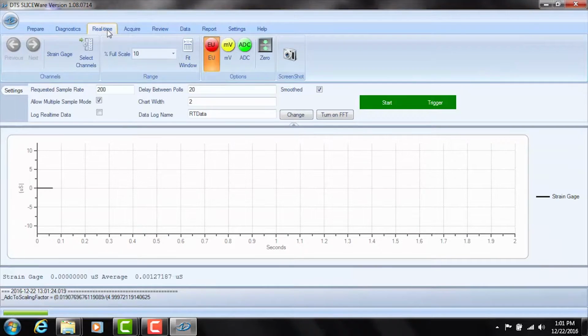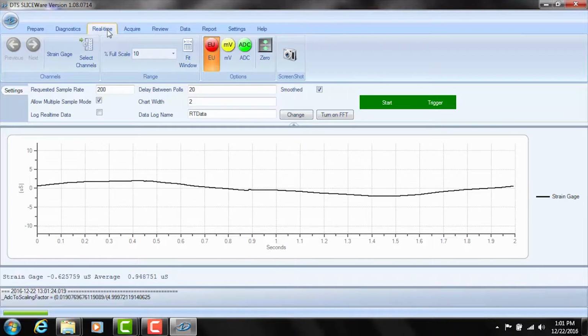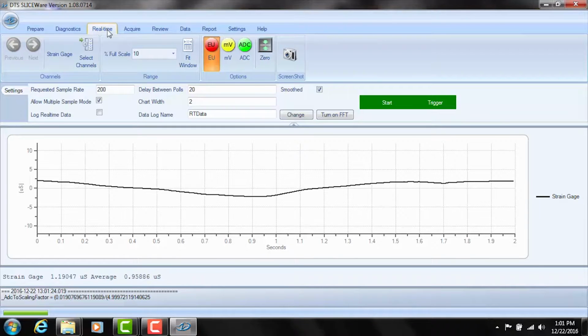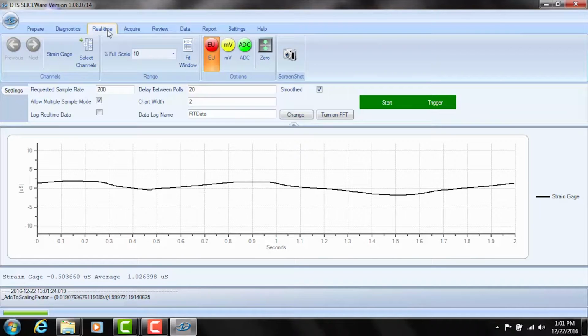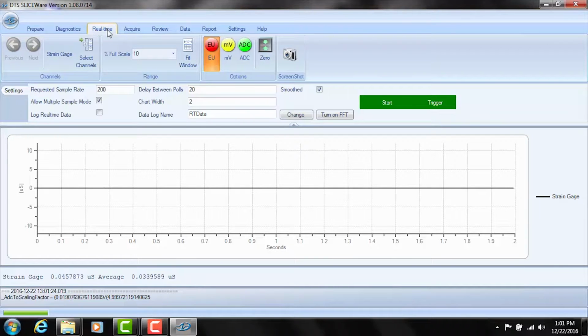Next we'll go to real-time. Real-time puts up a strip chart graph that's looking at data in real time right now. I'm going to flex the strain gauge sensor because that's what's being shown here. I've got a beam with a strain gauge attached to it, and I'm flexing that beam, and we can see deflections moving like we should. So that's all good. You can do this for each sensor that you have connected. It's a way to make sure what you're looking at makes sense before you actually run the test. Okay, now I'm going to shift over to the Acquire tab.